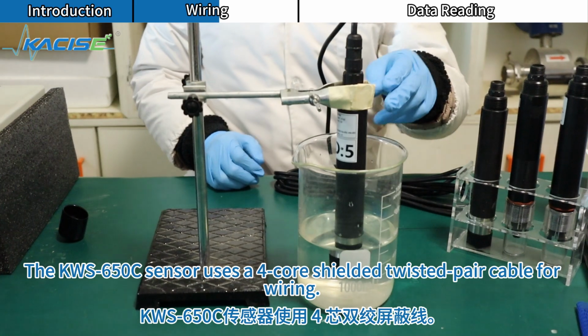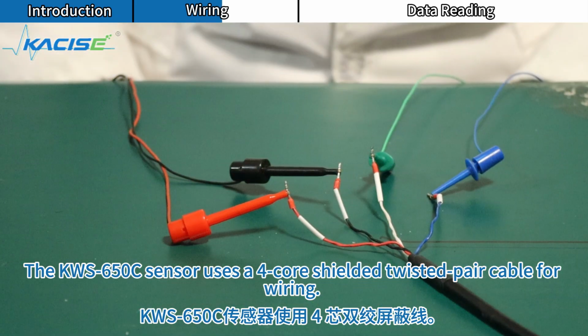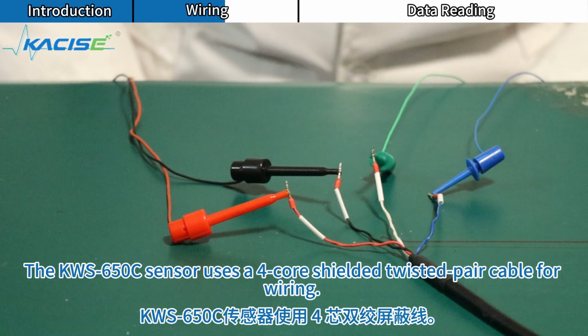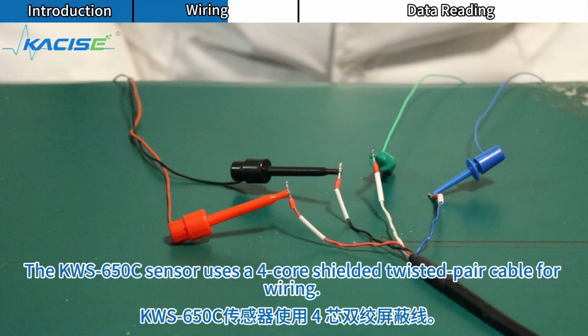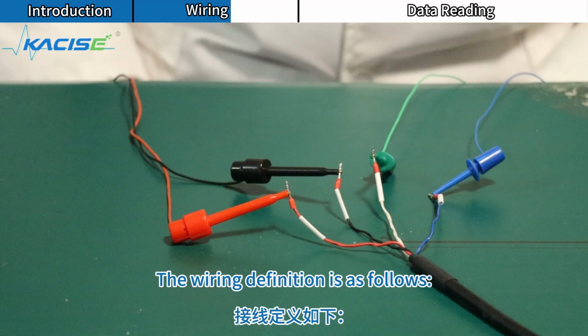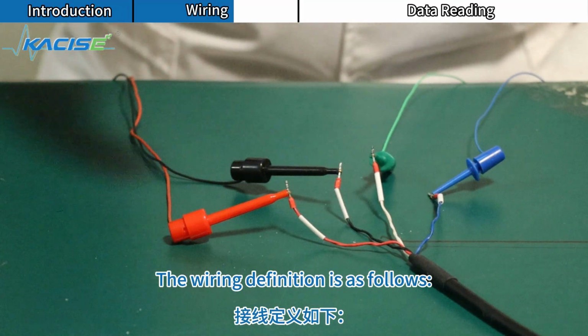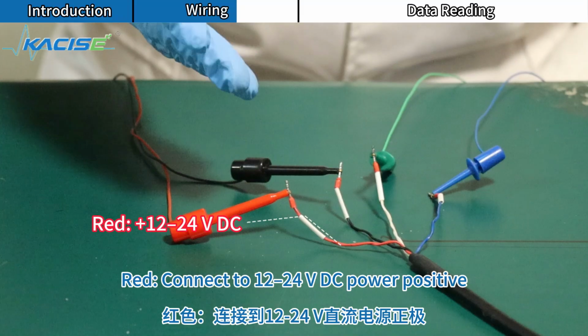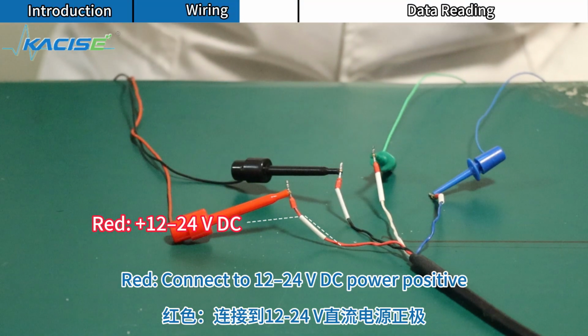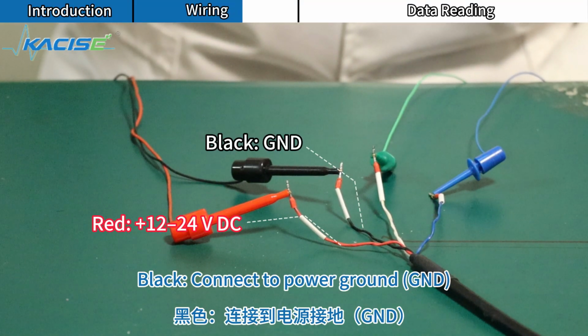The KWS-650C sensor uses a 4-core shielded twisted pair cable for wiring. The wiring definition is as follows. Red, connect to 12 to 24 VDC power positive. Black, connect to power ground, GND.